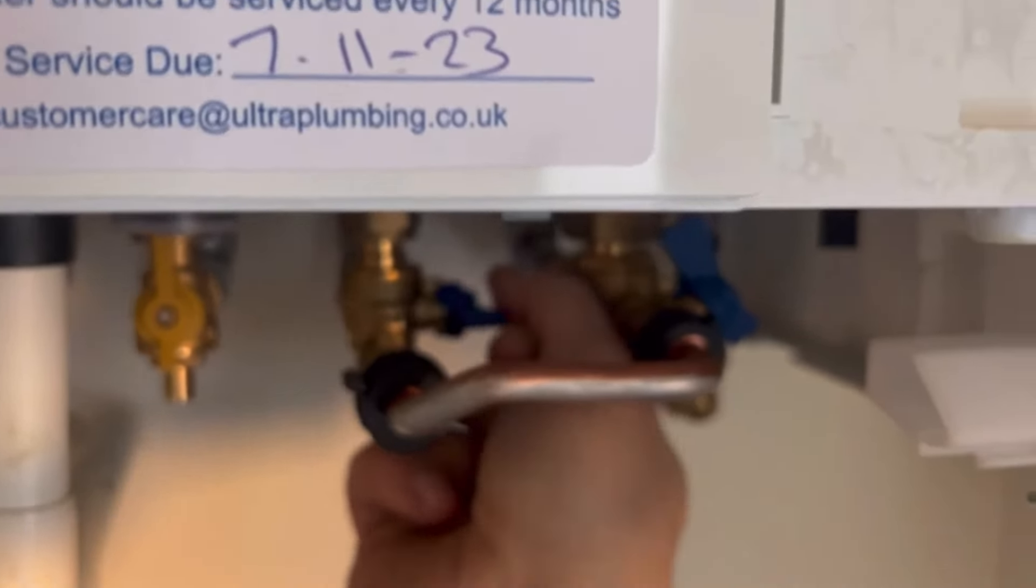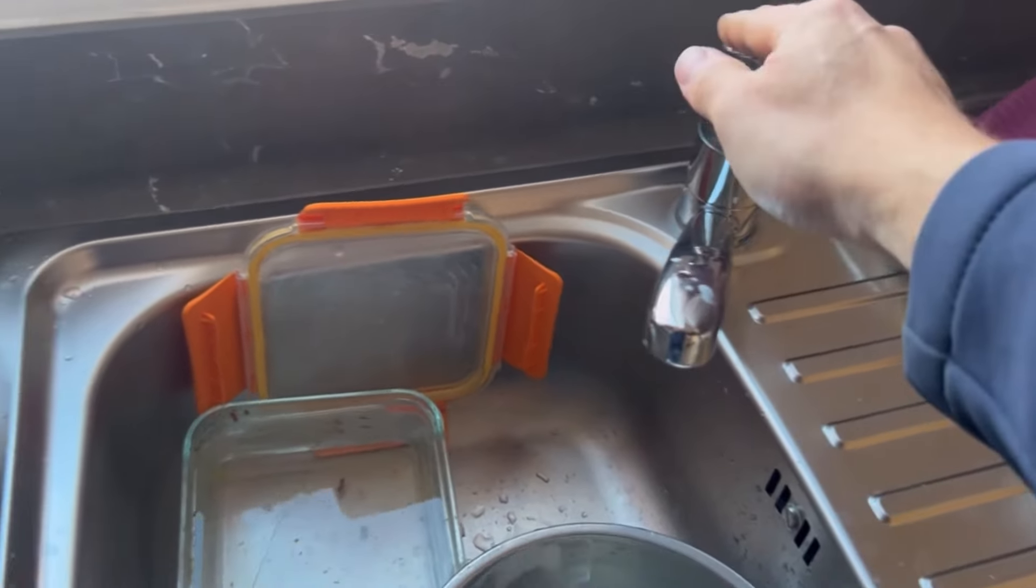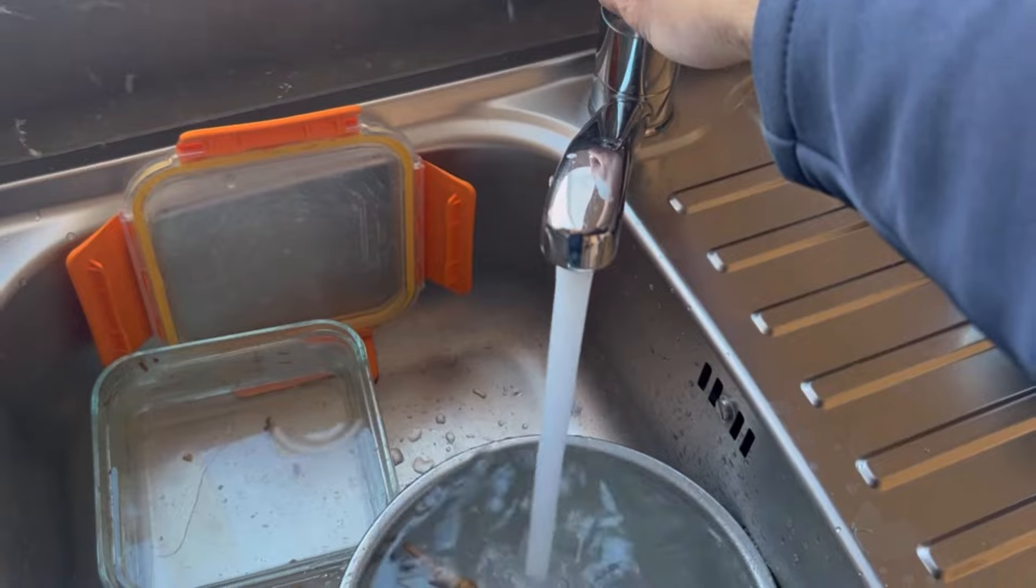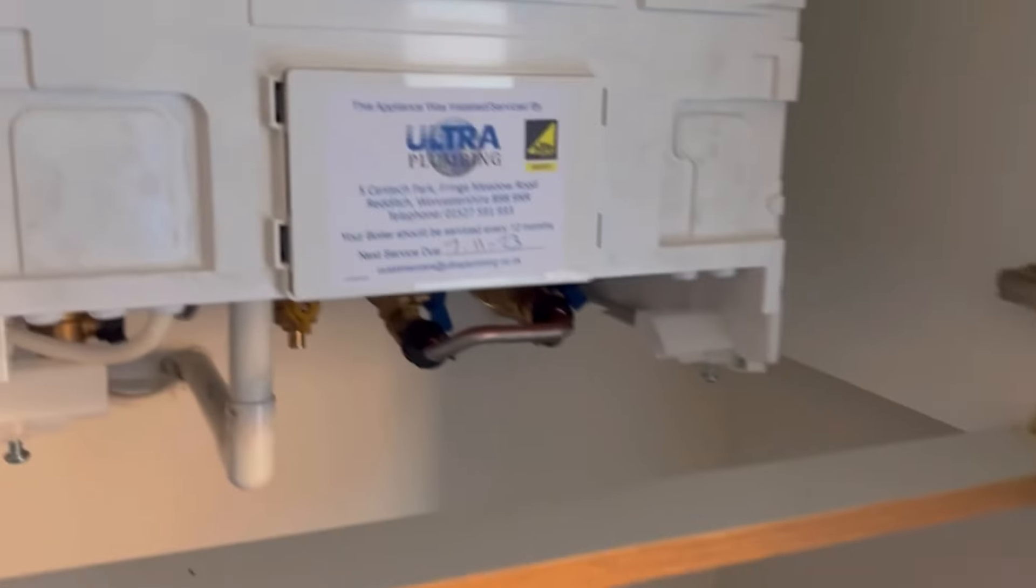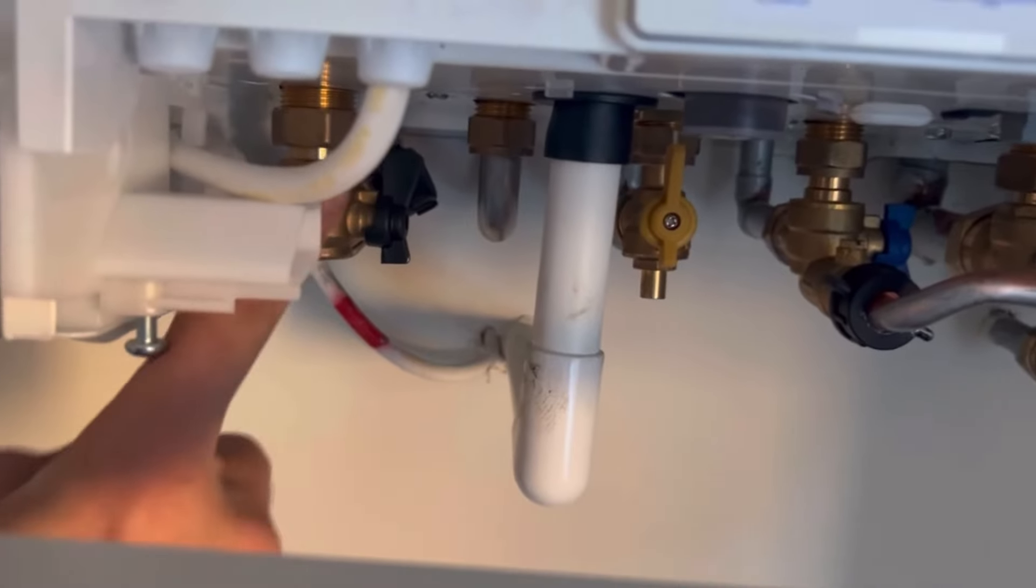Now if we have that facing the wrong way, i.e., like that, then what will happen is no water coming out of your hot feed. So we're going to turn it back, and voila, there's your water. So that's a common call we get - no hot water coming out of taps.